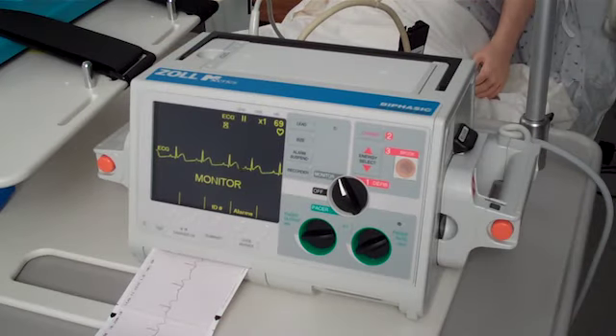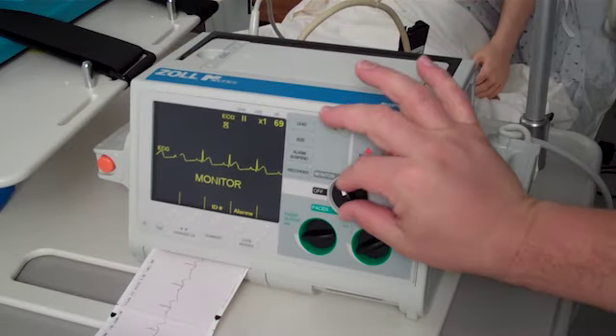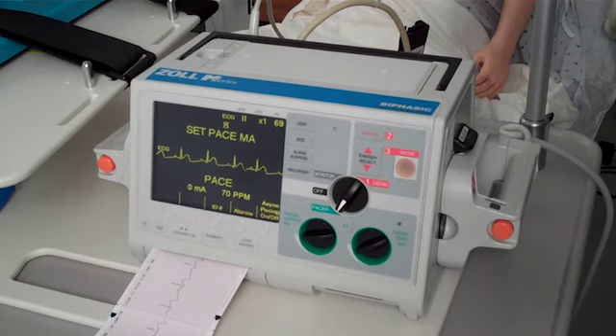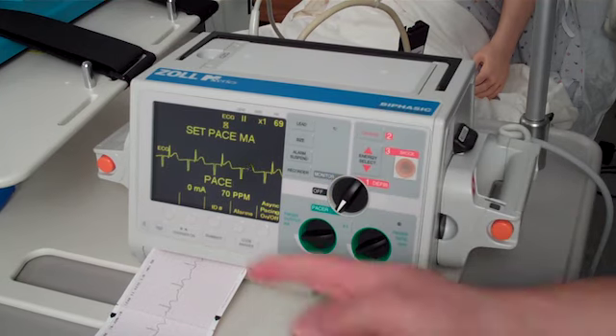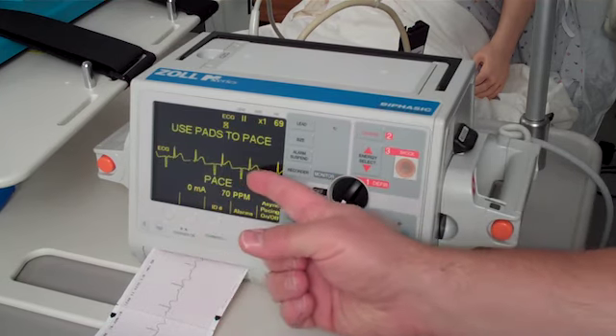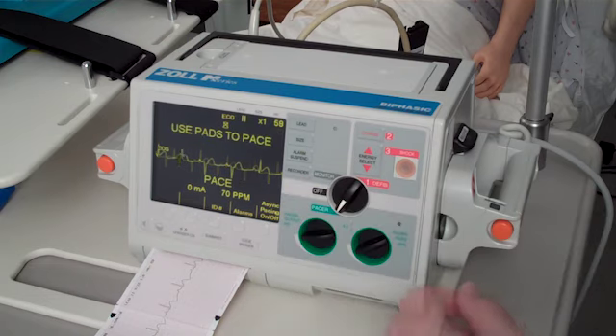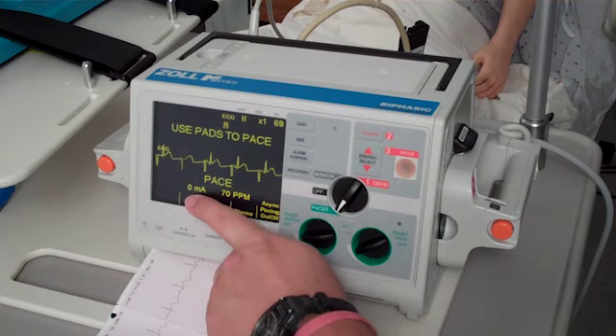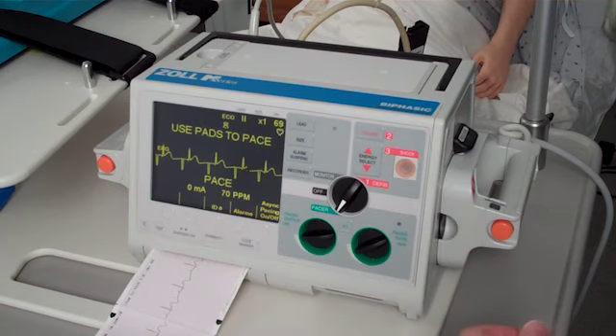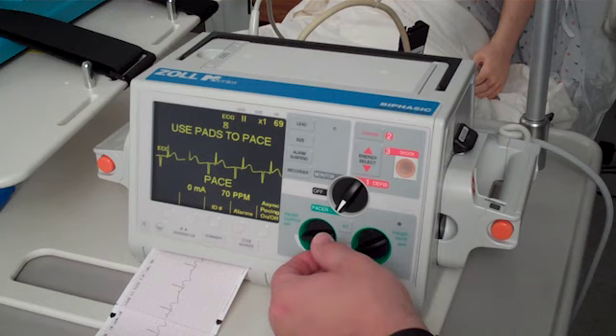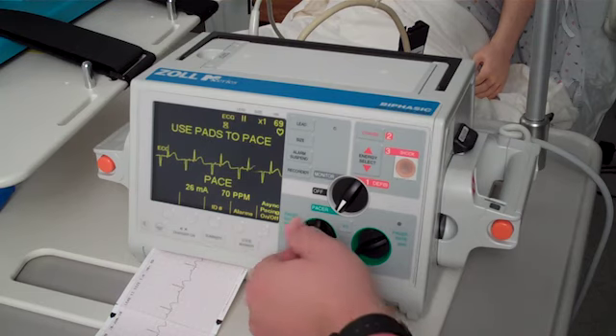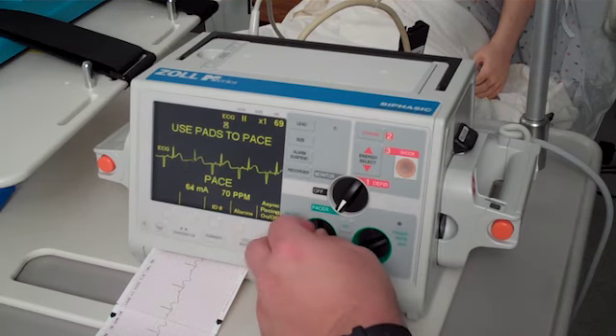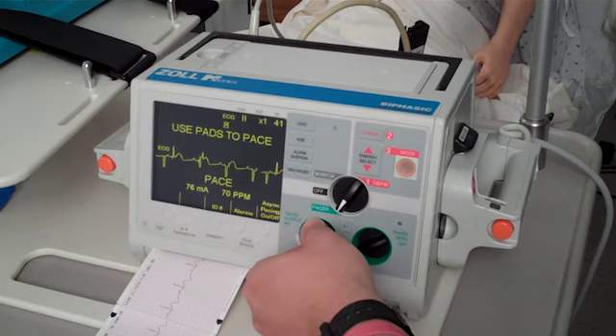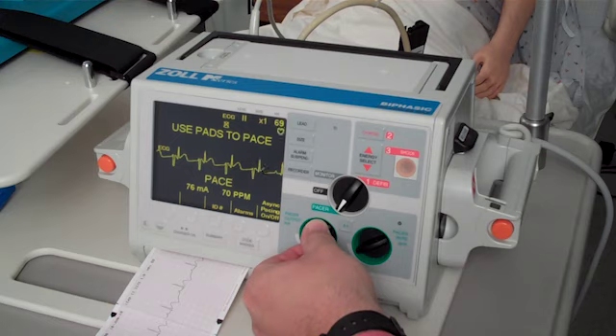Should the patient require pacing, turn the dial to the pacing section. As you can see, the pacer spikes have appeared before each of the QRS complexes. The rate is set for approximately 70 beats per minute. The milliamperage energy setting is usually set at 0 to begin with. Increase the milliamp setting until capture is achieved, usually somewhere in the neighborhood of between 70 and 100 milliamps.